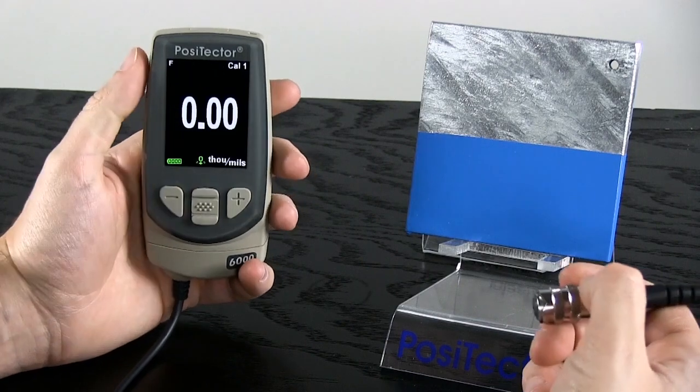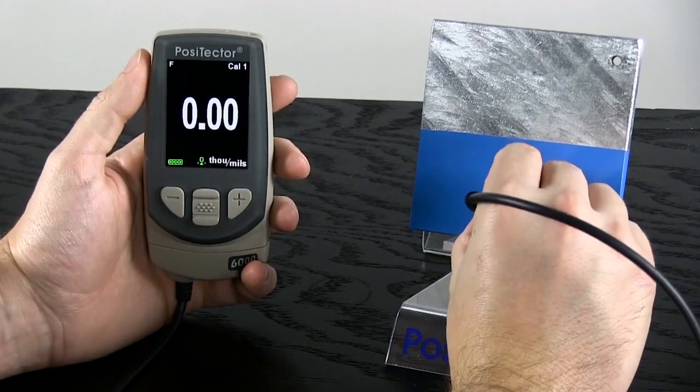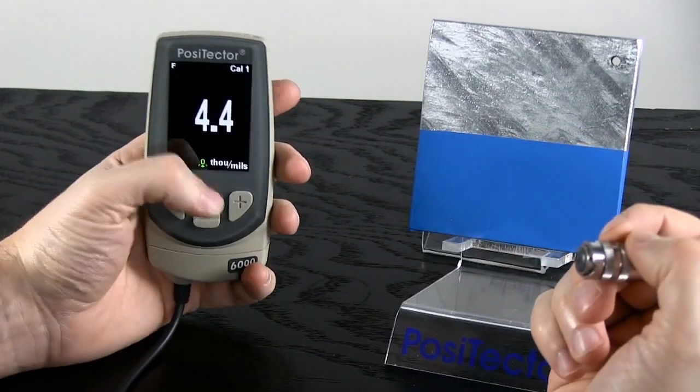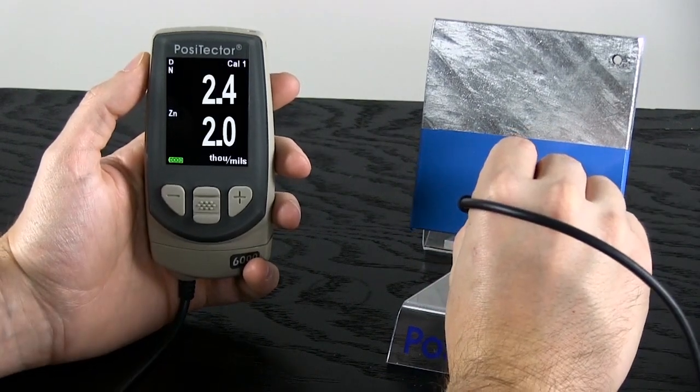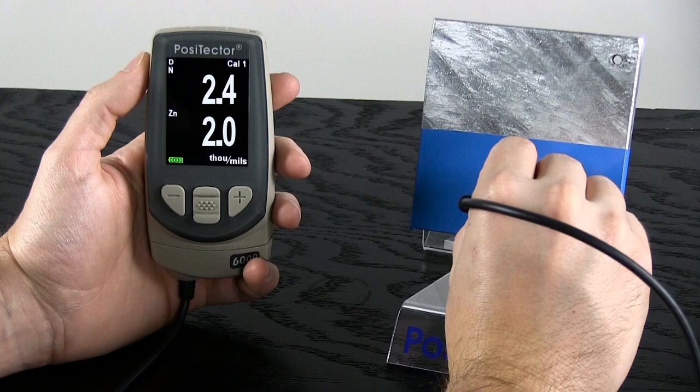With duplex mode off, the probe measures the total thickness of the coating system. With duplex mode on, the probe measures the two individual layer thicknesses.